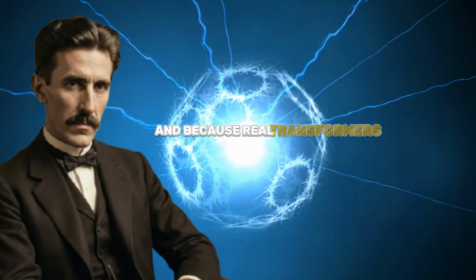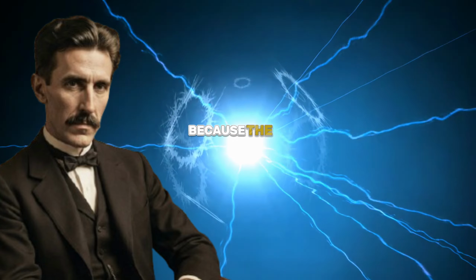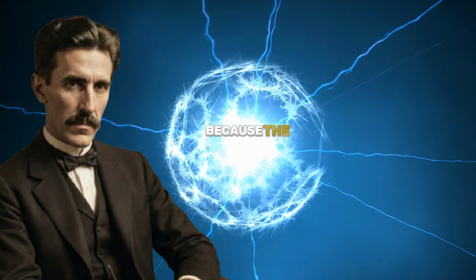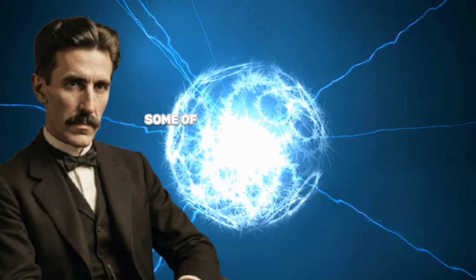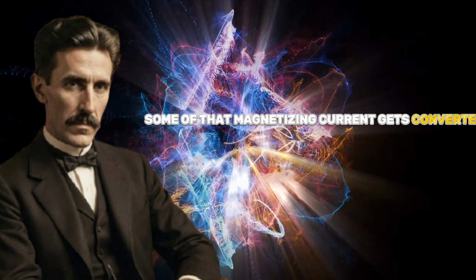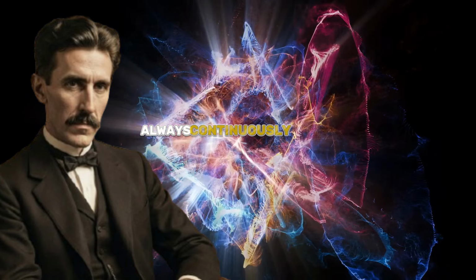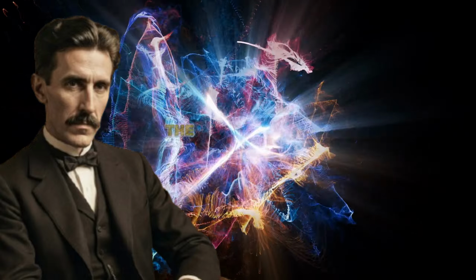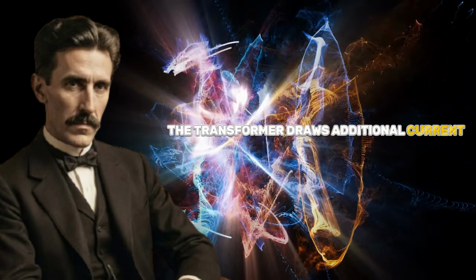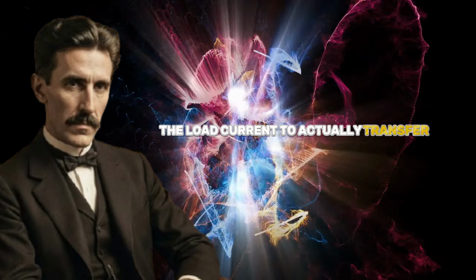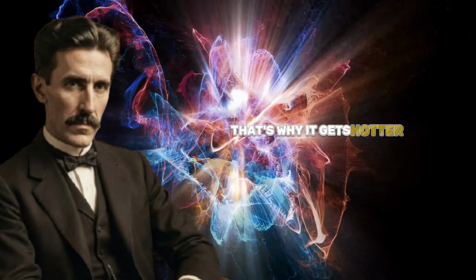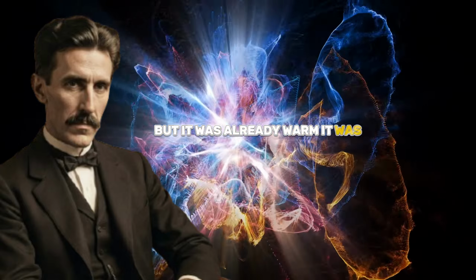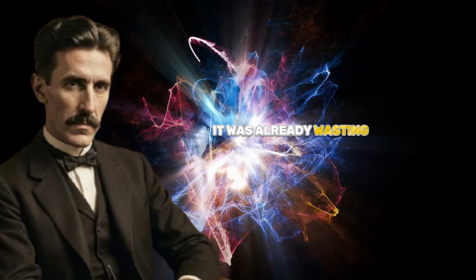Because real transformers aren't perfect, because the iron core has resistance, because the wire has resistance, some of that magnetizing current gets converted to heat, always, continuously. When you connect your phone, the transformer draws additional current, the load current, to actually transfer power. That's why it gets hotter. But it was already warm, it was already working, it was already wasting energy.